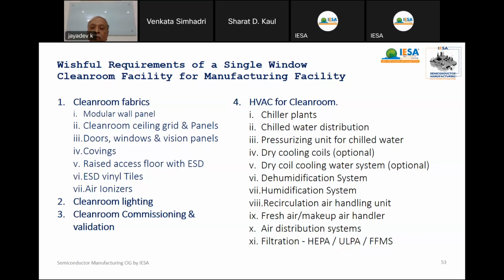That air has to be pre-cooled, with moisture content removed, and then sent into the dehumidifier, where the dehumidifier further reduces moisture content, and then supplied into the recirculation unit at the required grains per pound of air that is conducive for use. Similarly, humidification also plays an important role. If it goes below 38% RH, a lot of static charge will build up. So we have to use a fan type humidifier, which sprays water vapor when it goes to 38% RH.